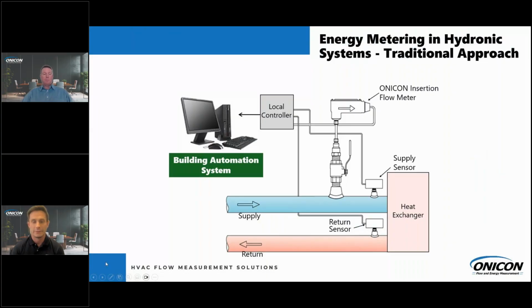What we have here is a representation of the traditional approach for energy metering in hydronic systems. As you can see, the supply and return temperature sensors, the local PLC controller, and the flow meter, which typically was an ONICON flow meter because it is the gold standard.